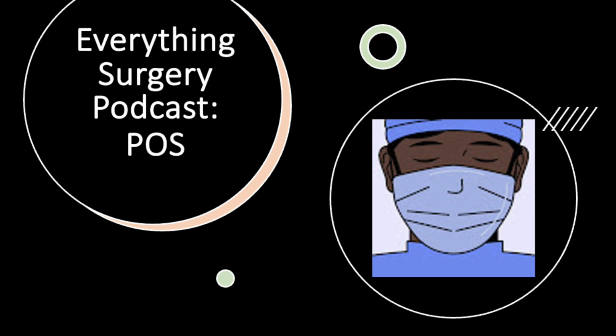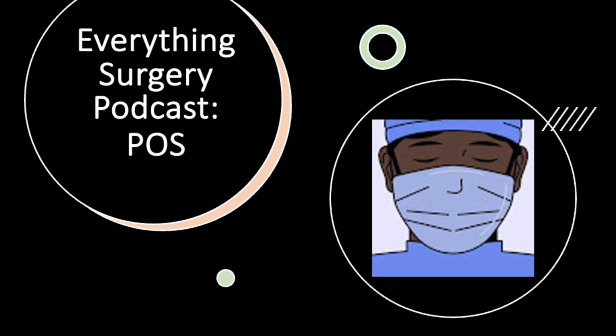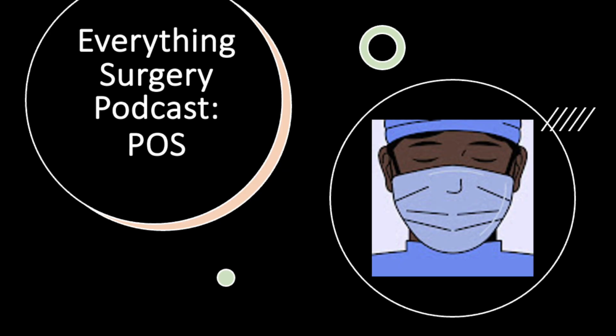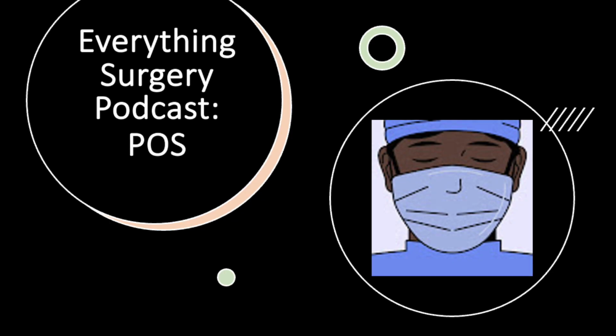Dry heat sterilization works by oxidizing cell components. It is used for items that would be damaged by moisture, such as powders, petroleum products, or sharp instruments susceptible to corrosion. While it is non-corrosive and penetrates well, cycle times are very long, ranging from 1 to 2 hours at 160 degrees Celsius, to 6 to 12 hours at 120 degrees. High temperatures can also damage many materials.